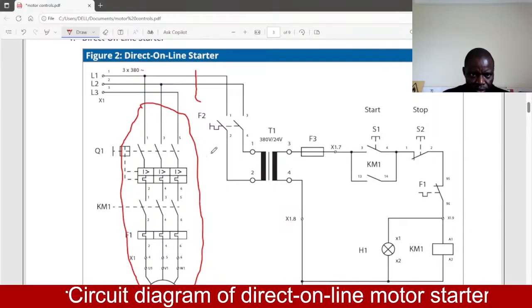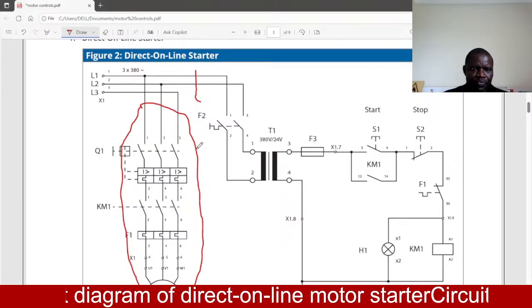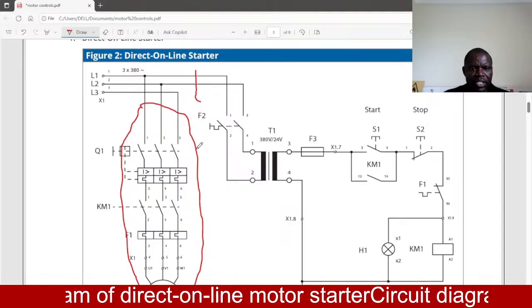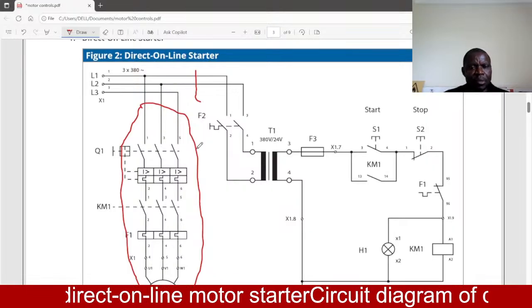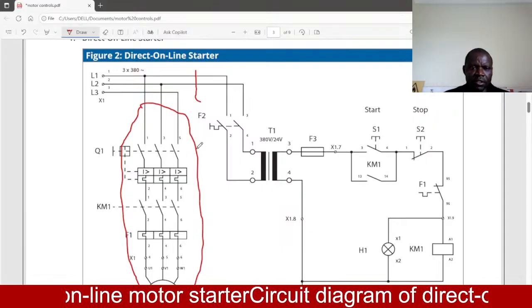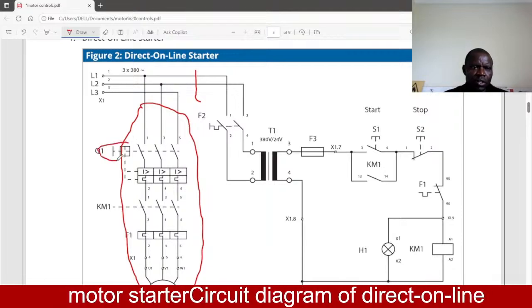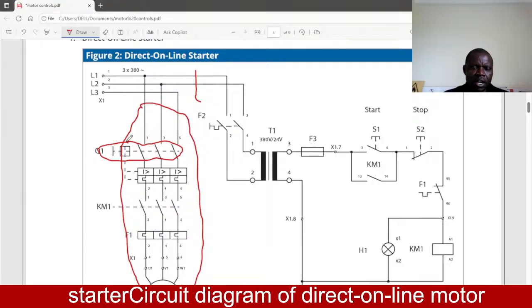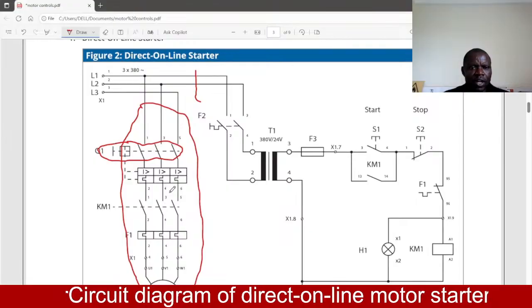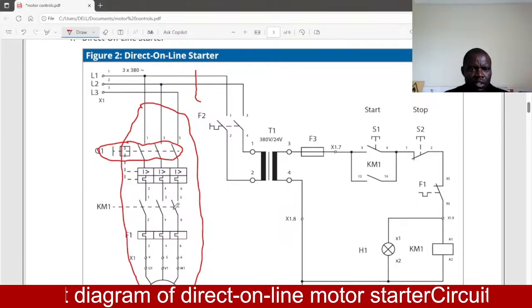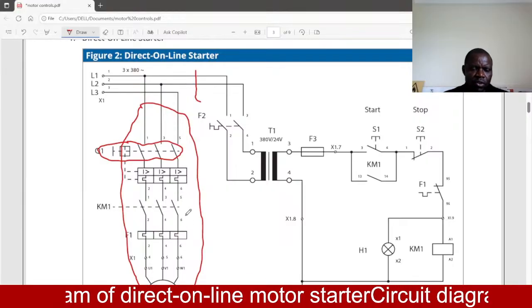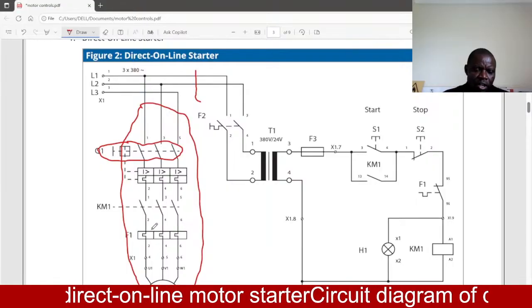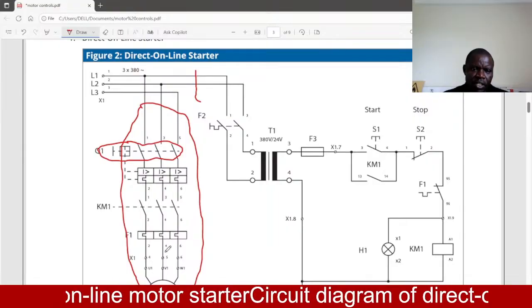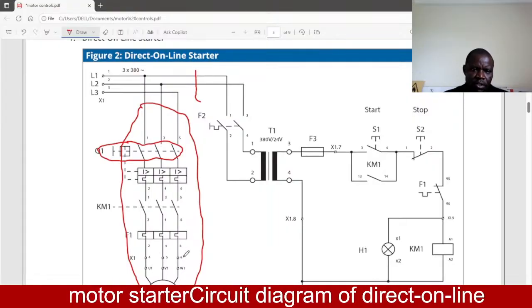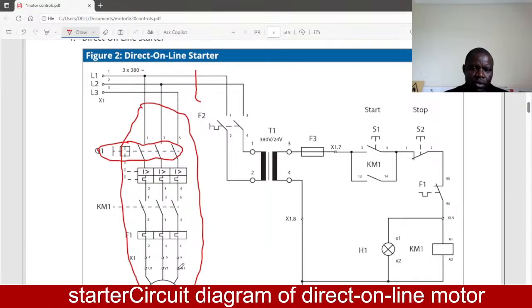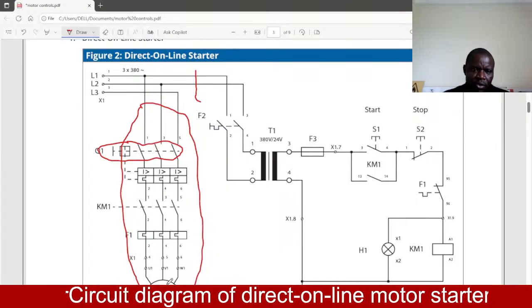Now, the main circuit is composed of a contactor and an overload relay plus the circuit breaker or the main switch that controls supply. So when you look at this one here is our isolator or circuit breaker. Then we have these contacts here named 1, 2, 3, 4, 5, 6. This one forms the contactor terminals. Then this one here, F1, is our overload relay. And from 4, 5, 6, then you have V, U, W. These are terminals of the motor. And down here is the motor.